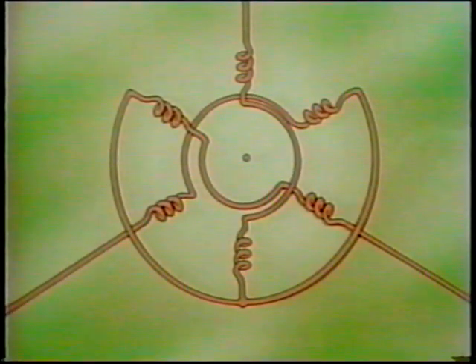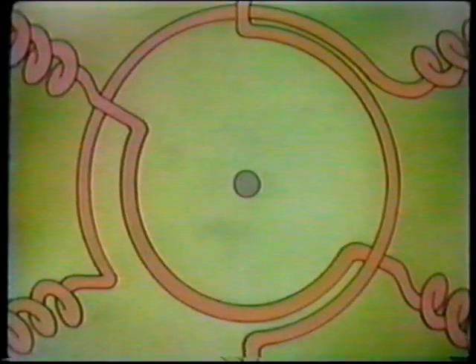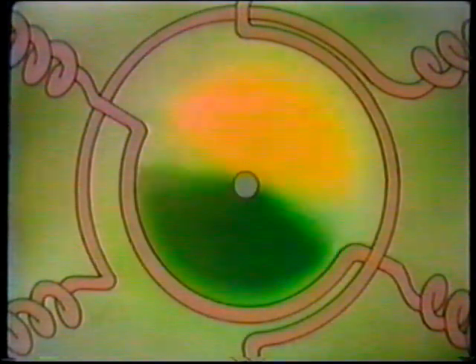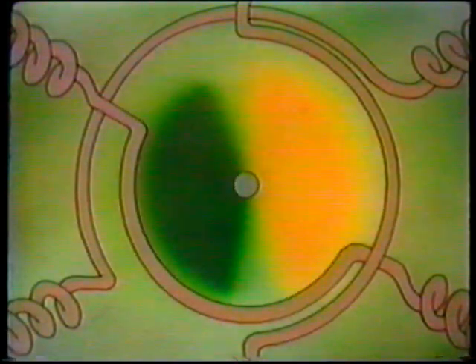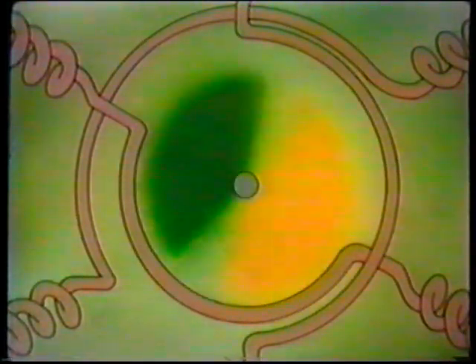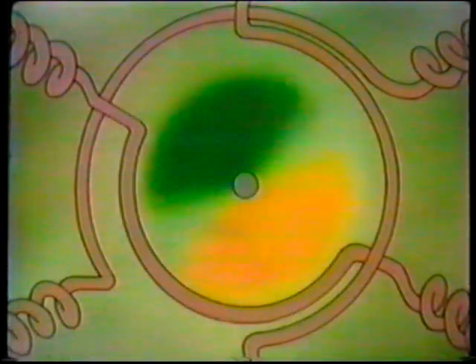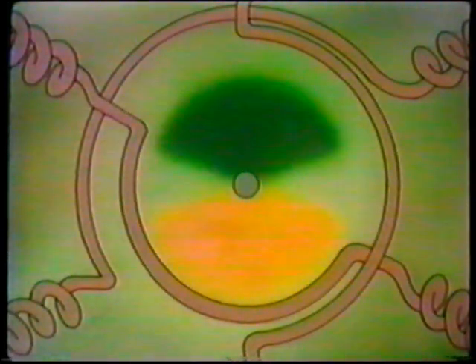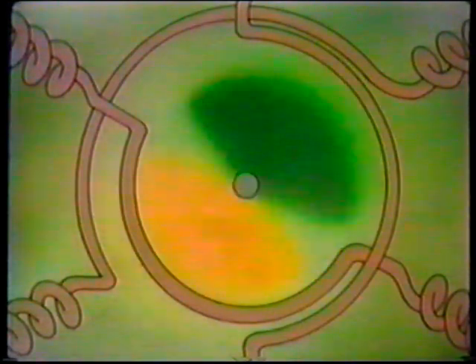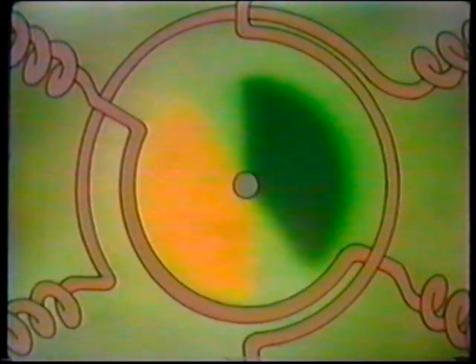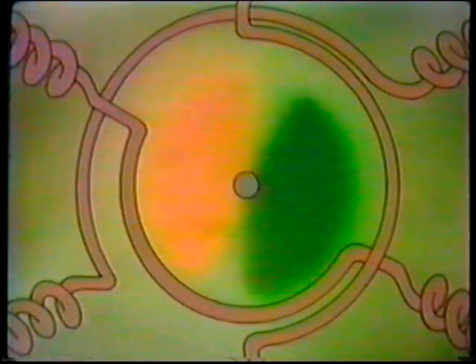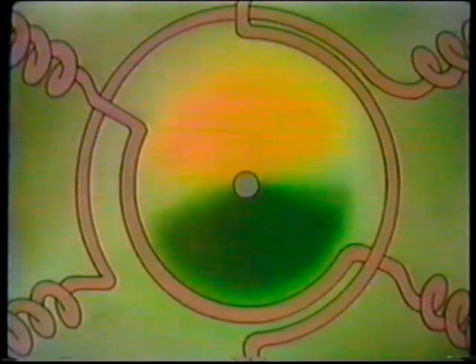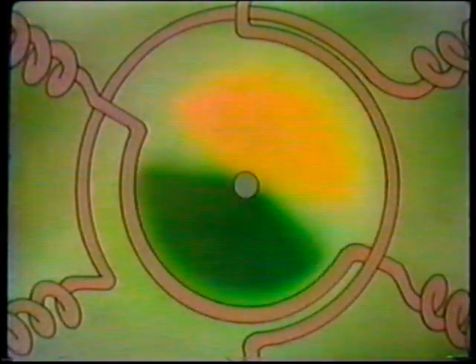In a two-pole synchronous motor, there is a coil pair for each phase of three-phase alternating current. As each phase of current flows through its coil pair, it produces a magnetic field with a north and south pole. Here the magnetic poles are represented by the colors green and yellow. The strength of the magnetic field for each phase increases and decreases along with its current, and its magnetic poles reverse when the alternating current changes direction. The net result is that a rotating magnetic field is produced in the stator. The speed at which the magnetic field rotates is called synchronous speed, and a synchronous motor is an AC motor that operates at synchronous speed.